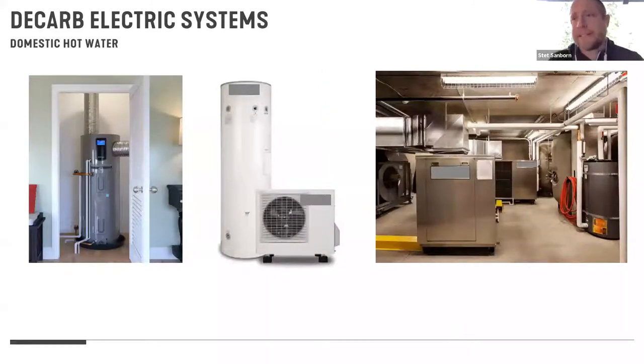On the domestic hot water side, this is the area I will say is changing the fastest and the most. And it's what most of our technical committees out here are working on, better design guides around domestic hot water. So as we move off of condensing water heaters, gas-fired water heaters, we're seeing a market shift towards either monoblock or singular unit type heat pumps that are either using indoor air or ducted to the outside. In our climate zone, ducting to the outside provides a great benefit for most of the year. But in more humid areas, like the southeast of the US, you might actually want to duct these from inside air and get that benefit of dehumidification inside your unit as well.